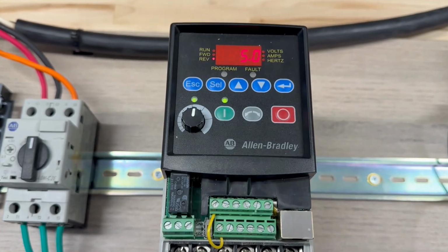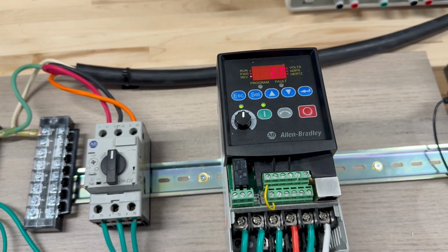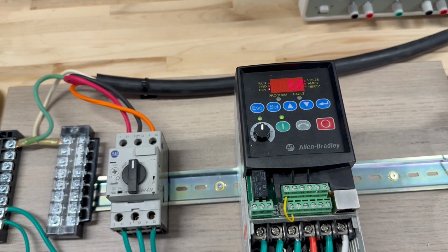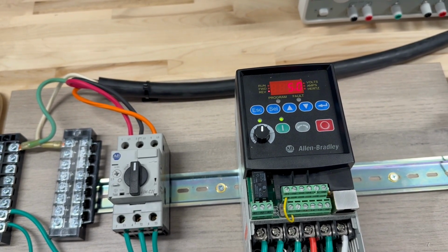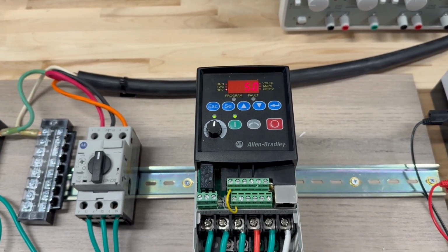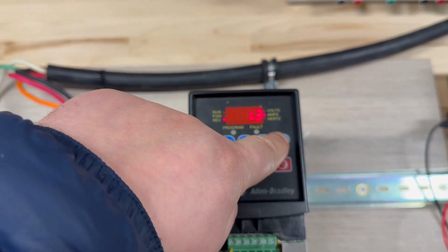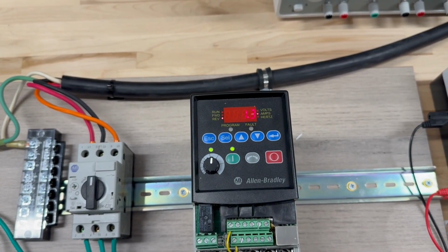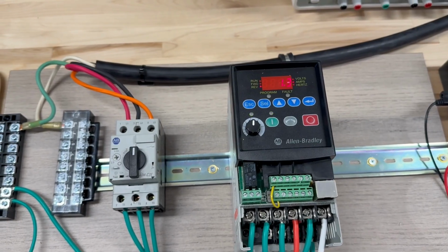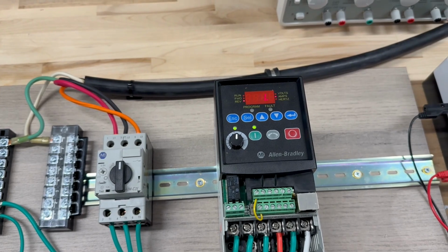So enter, I already put the 5, so it means 5 seconds should be the time that we have the inject brake time. And the A81 is the next one, which is a DC brake level. How much DC current you want to inject in that 5 seconds. So should be 81 as you see, and I put on 1.3, so 1.3 amp, which is the level of the actual DC injection. So now I think we are all set.